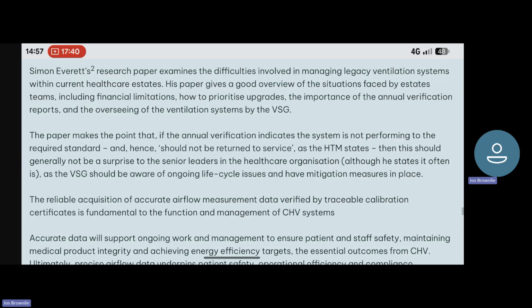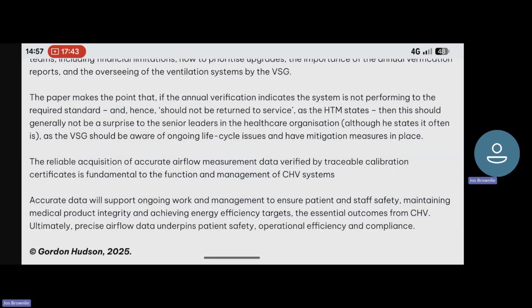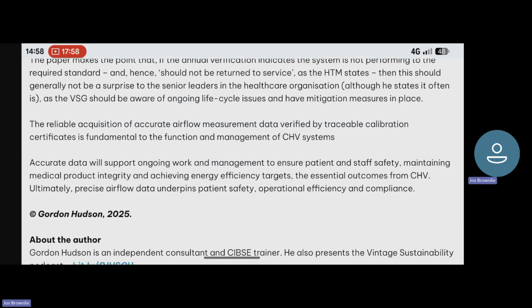The paper makes the point that if the annual verification indicates the system is not performing to the required standard and hence should not be returned to service as the HTM states, then this should generally not be a surprise to the senior leaders in the healthcare organisation, although he states it often is, as the VSG should be aware of ongoing life cycle issues and have mitigation measures in place.